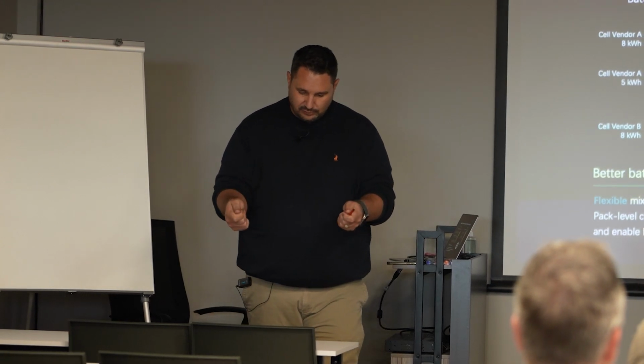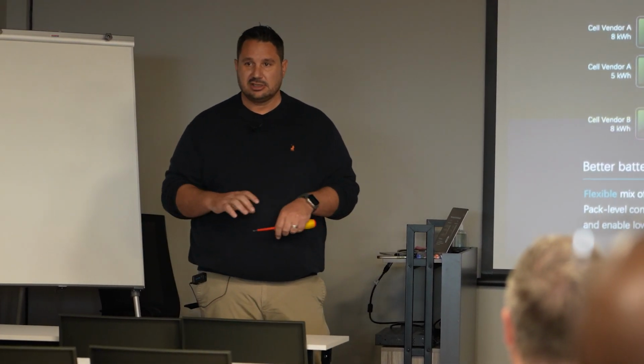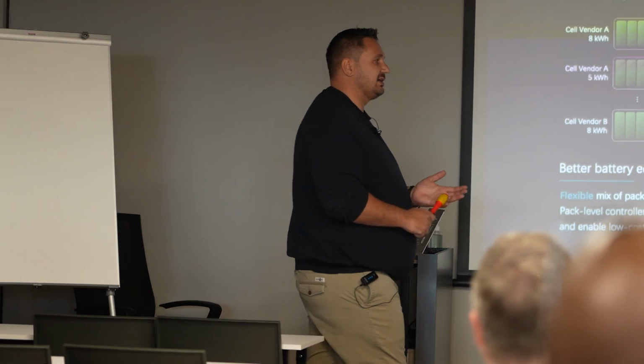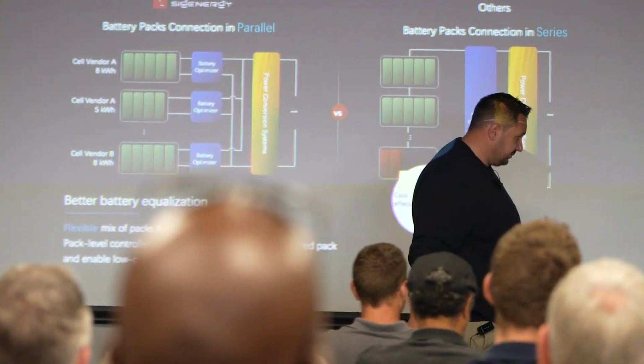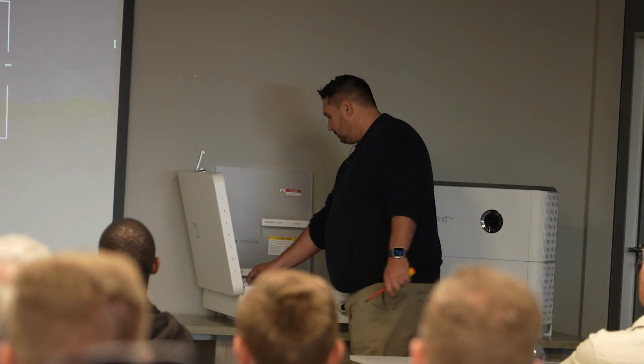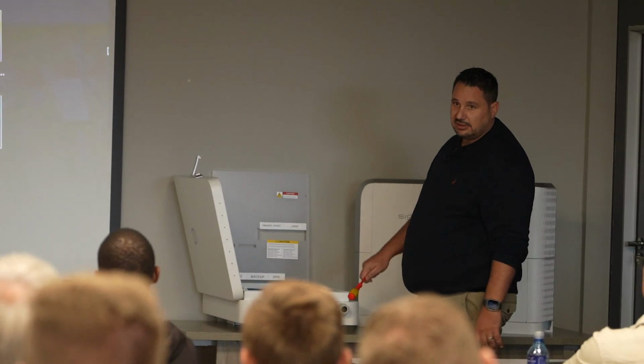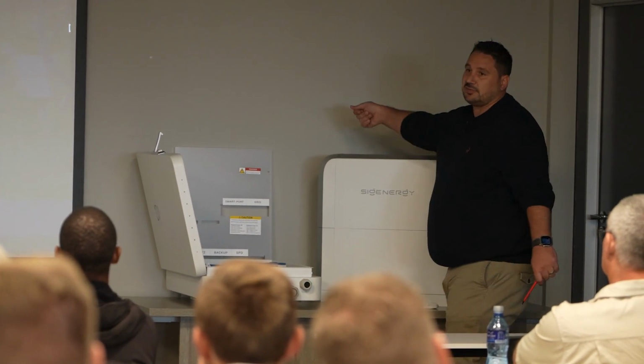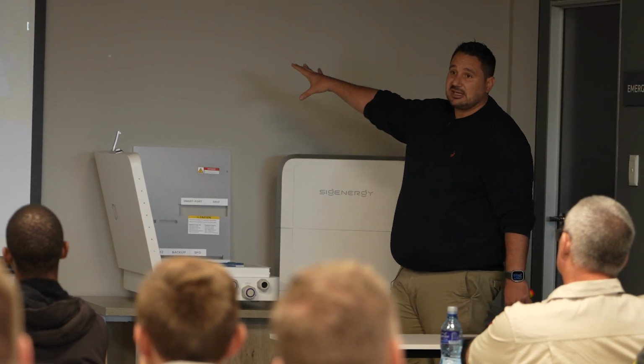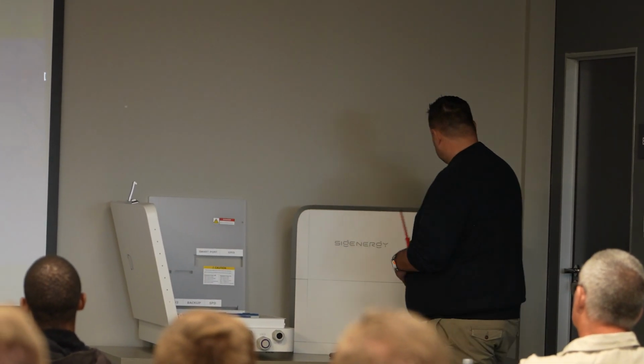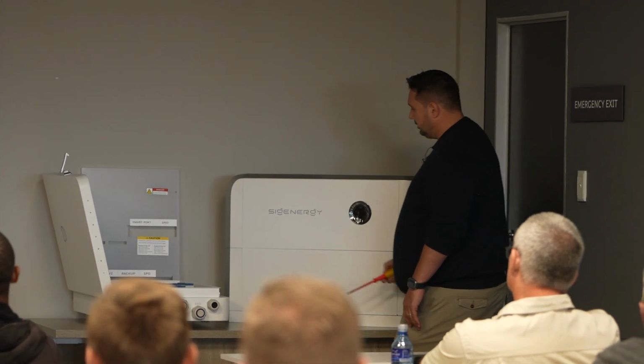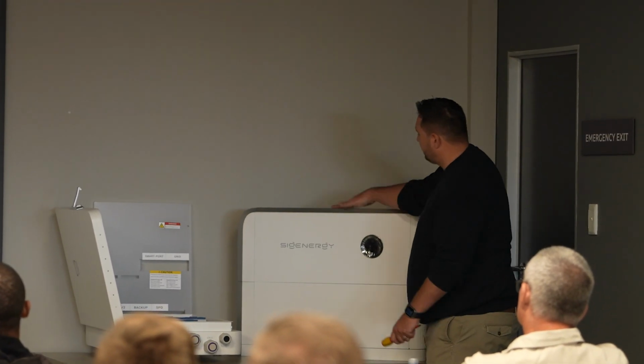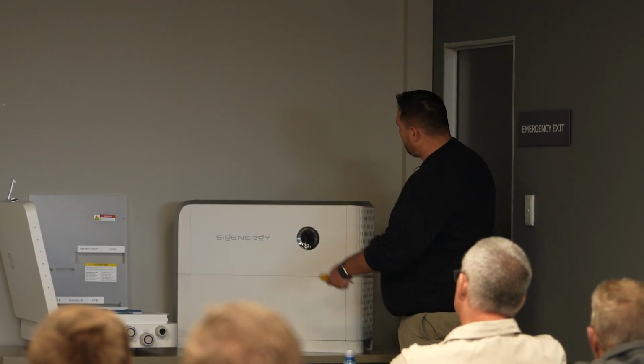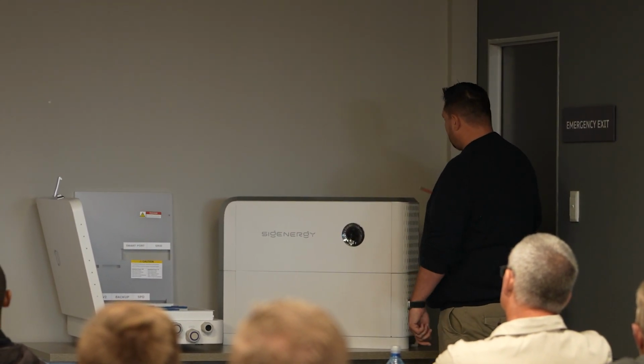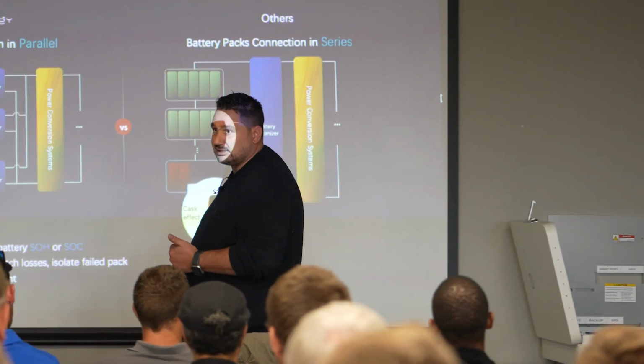Once you remove the old battery or you add the new battery, so let's say you've got a customer that's got a 6 kilowatt inverter with an 8 kilowatt battery. All you have to do is you come to your gateway, you switch off the inverter. So when the inverter has been switched off, this will get power down. You switch off the DC side, press the button, it's dead. Power stays on because it's gone back to grid now. Take off these covers, 3 screws here, 3 screws here. Take off the inverter. As you take the inverter off, you put the next battery down, put the inverter on top, 3 screws, switch on, leave. That's it.